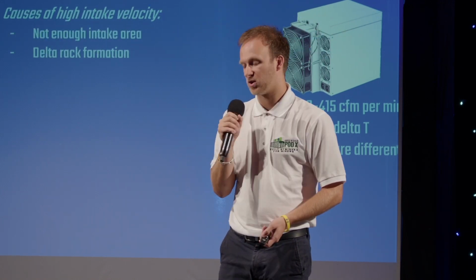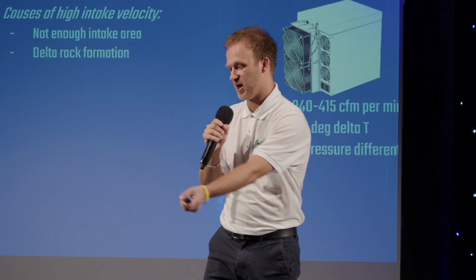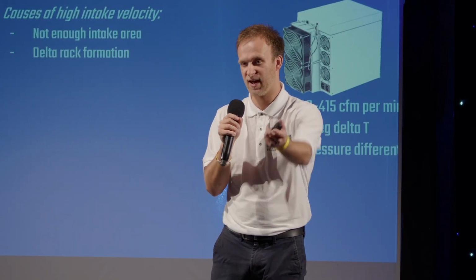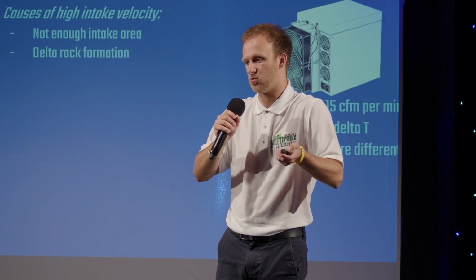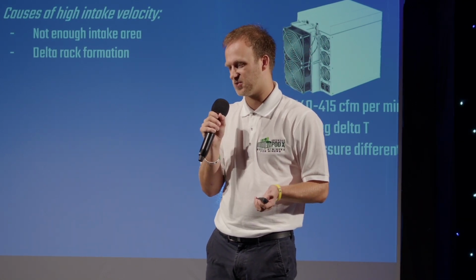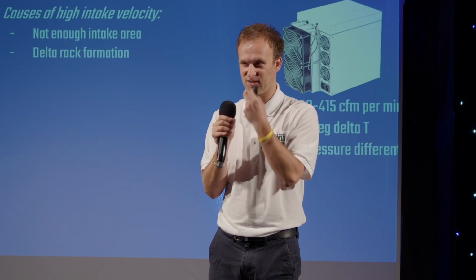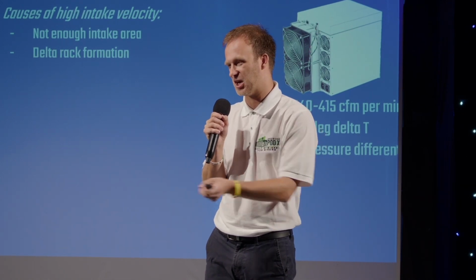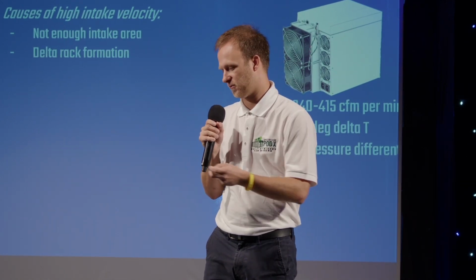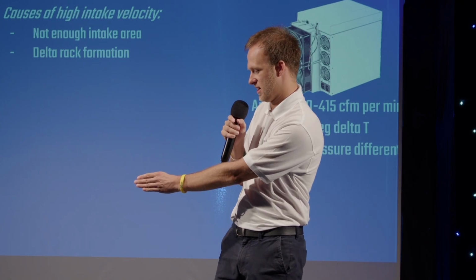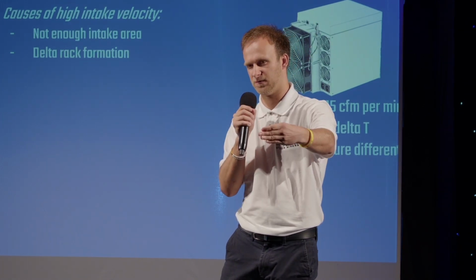So what causes high intake velocity? Your miner is going to be pulling in at 415, but that air is still coming in way too fast. So why is that? It's because of two things that we've come to realize. One of them is not enough intake area, from your miner intake grill all the way to your filter or louver.